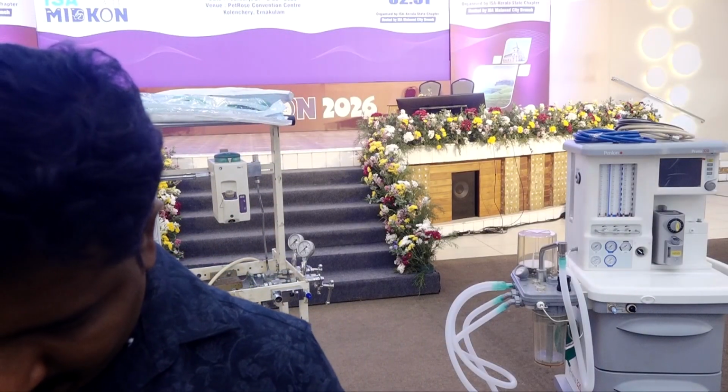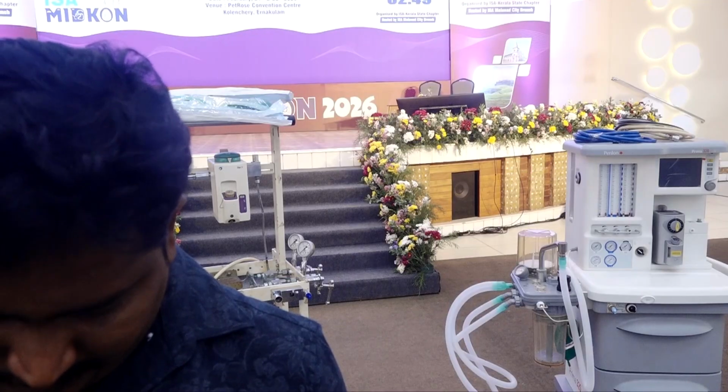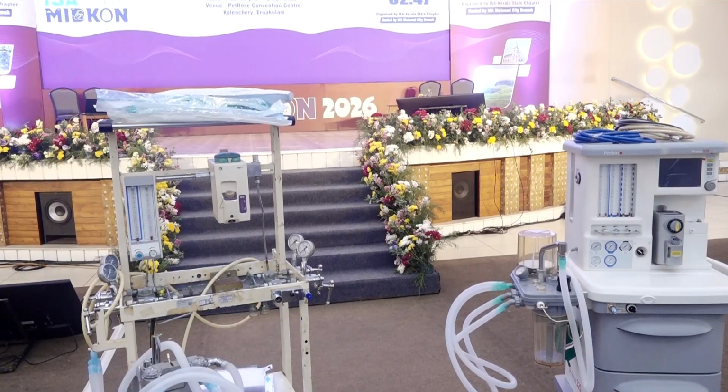So especially with Draeger machines with a piston-driven ventilator, when you activate it during mechanical ventilation, because there is a fresh gas flow decoupling valve in Draeger, when you operate the flush, the oxygen cannot directly go to the patient. It will go only to the bag. That is the advantage of the fresh gas flow decoupling valve which is present with Draeger. So the bag can burst but not the patient's lungs.